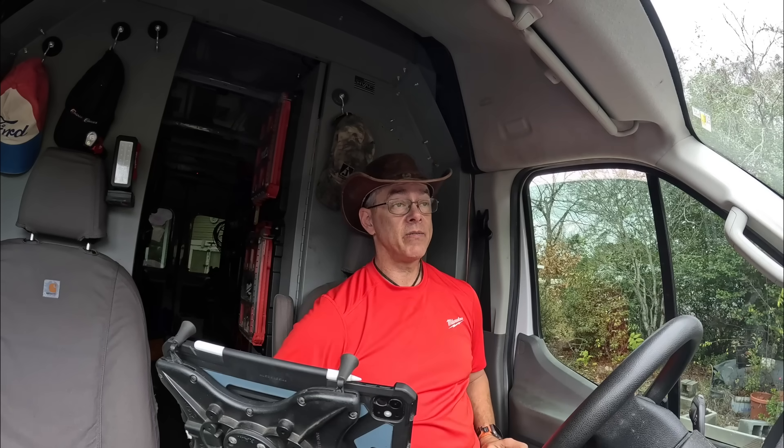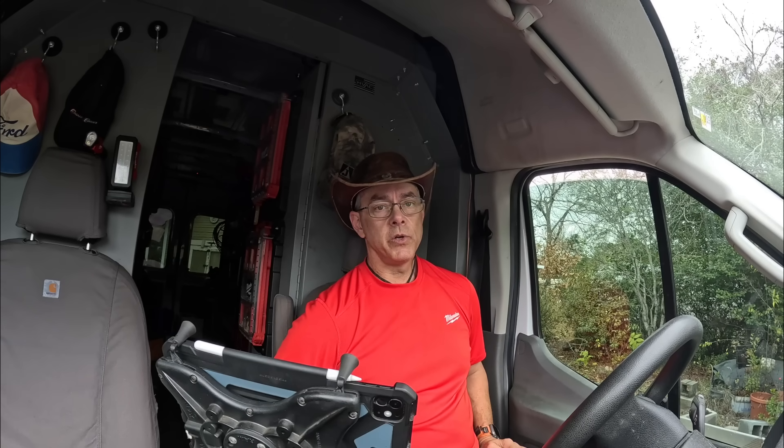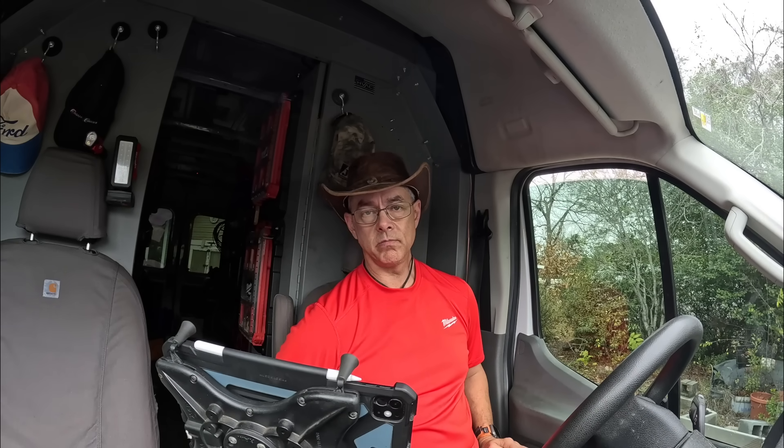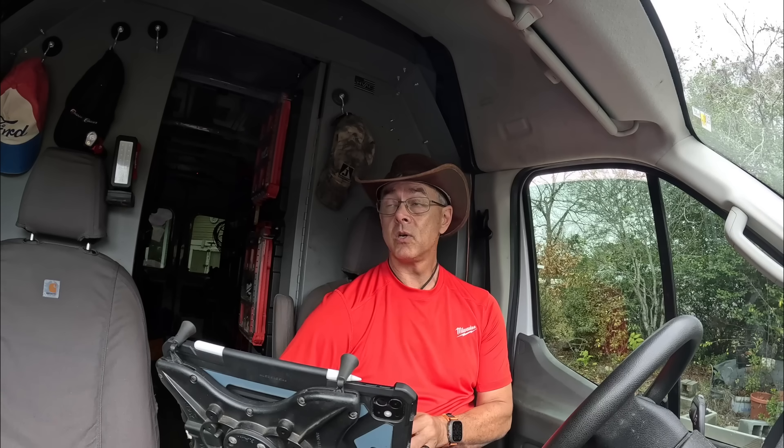This gives me a total square footage of this area of 2,036 feet. So basically what I've come up with is that a 4-ton will do, but if I increase the design temperature to 97 degrees instead of 95 outside, it's a little bit over 4-ton. So a 4-ton is just barely big enough. What I would like to quote this customer is maybe a 5-ton that is variable speed - that way when it's really hot the 5-ton can keep up. I'm going to quote him the 5-ton variable speed, line set, drain pan, pad, new thermostat, new thermostat wire, especially if I quote him a communicating system. I'll talk to him about it and see what he wants to do.